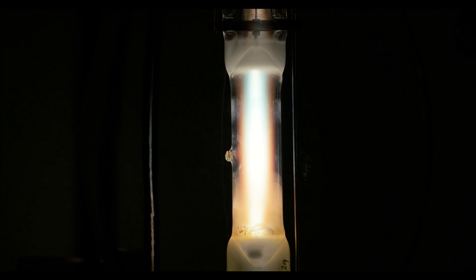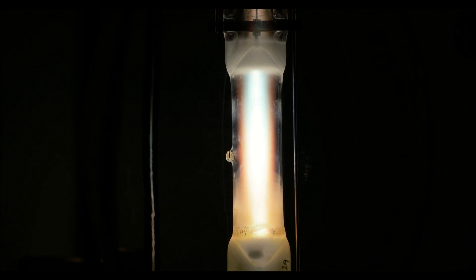Right, there's the lamp at full power. It's quite a nice fat arc—must be a fair amount of sodium in it. There is a bit of colour segregation, you can see at the top compared to the bottom where most of the highlights are. The arc current of this lamp is 4.1 amps with an arc voltage of 264 volts. It lasts for 12,000 hours and puts out 110,000 lumens, colour temperature of 4000 Kelvin with a colour rendering index of 68%. So let's have a closer look at the arc.